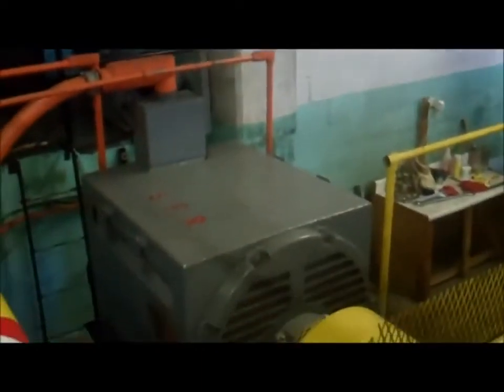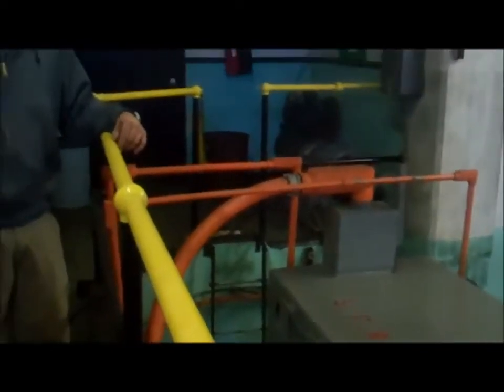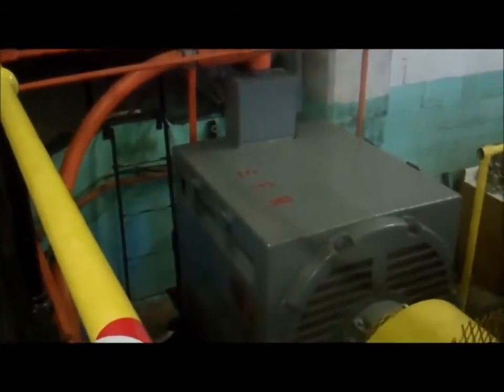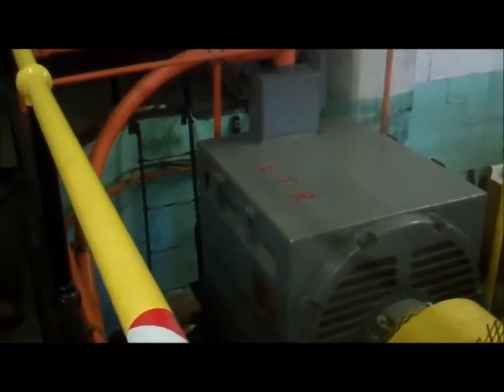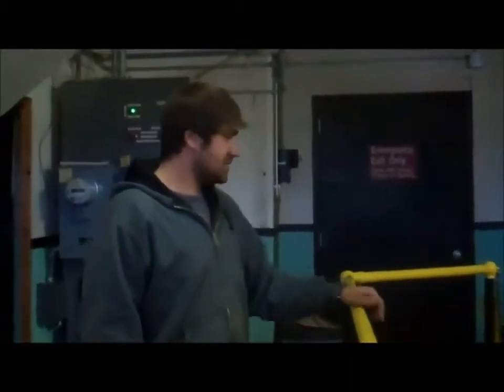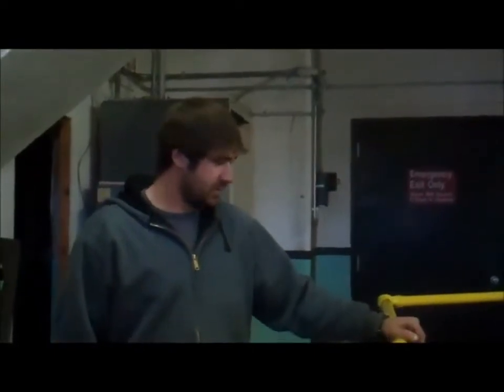Because these are synchronous machines, when you put them online, you have to get them to the right frequency before you close the breakers, or you get a massive influx of power to the grid, or if you're going too slow, into the building. And it's pretty dangerous if that happens. And these are electromagnet, non-fixed magnet machines, so we have to apply a 48 volt DC current to the generator to actually get our 160 volt output out of it. So it's basically a giant car alternator, and it spins at about 1,000 RPM and creates our DC voltage for this machine. Each machine has one of these, but most of them are solid state, so it's a solid silicon thing now. These are the old-fashioned way of doing it with the alternator.